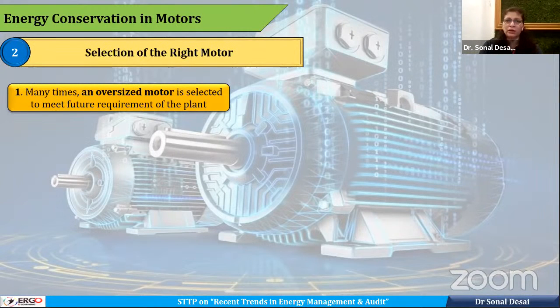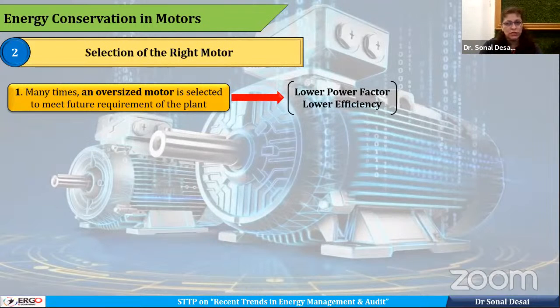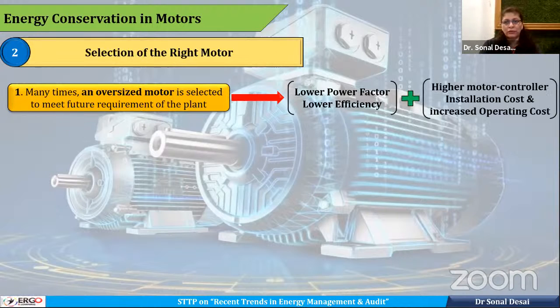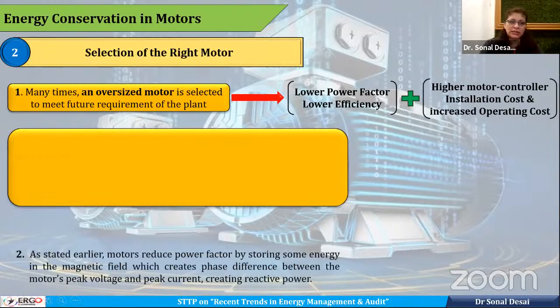pump or any other engineering application, if we make it run at an oversized condition, we are reducing efficiency as well as reducing power factor. By reducing efficiency, we are paying more electricity. By reducing power factor, we are paying penalty related to the power factor. So that will have higher installation cost, higher running cost, and increased operation cost.